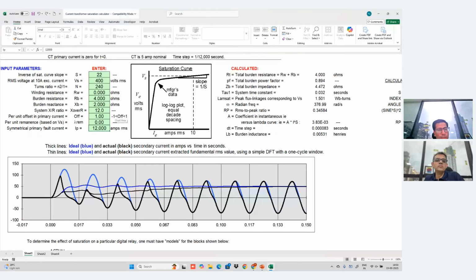Now, if I want to improve this, what I can do is, here you can see the voltage. The knee voltage is 400 volts. If I make it, let's say, 800, you can easily see now, because of the asymmetry, as I mentioned before, that at the starting the secondary current is a replica of the primary. But as the current goes further into the asymmetrical mode, then there is a difference again. And after a few cycles, when the saturation ceases, it will follow the secondary.